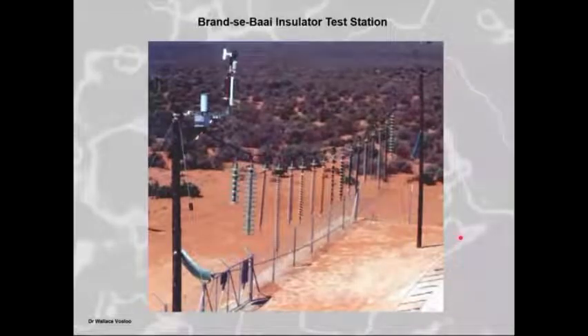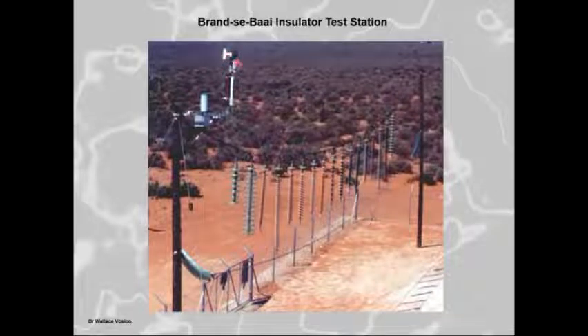Here's the test station we built. It was quite an interesting little one because we've got a weather station, we've got dust gauges, we've got all the climatic factors. We even measured solar radiation, rain, wind speed, wind direction, temperature, humidity, and so on. And then we also got a leakage current recorder where we measured all the leakage currents on these different options. So you can see we went actually quite ridiculous with some of them, but we also went for the blue ones and the gray ones and the red ones and all funny color ones and all the different types of glass, the open aerodynamic desert profile glass and the deep ribbed underfog glass.